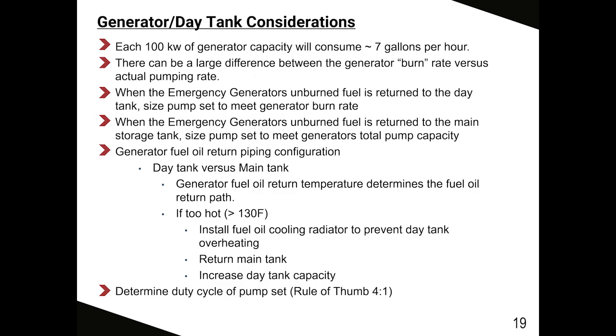Remedies for keeping day tank supply fuel oil cool: install a fuel oil cooling radiator to prevent overheating, return directly to the main tank, bypassing the day tank, or, if possible, increase your day tank capacity.